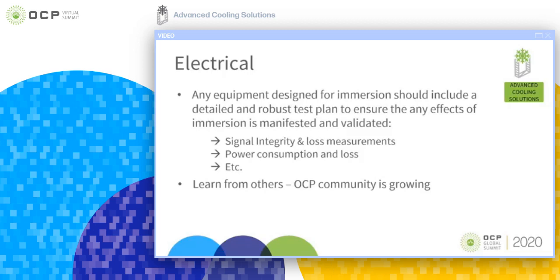bypass any of the due diligence that you do from a quality perspective for electrical design. So what's really important is to make sure that you've got a really robust test plan that looks at the key components of any electrical design: signal and circuit integrity, loss measurements, power consumption and loss, et cetera. What I would recommend is that as your test plan is fully baked out, you look at some of the key data points from your test plan in and out of immersion to make sure that you understand the deltas that you're starting to see from using immersion technology.